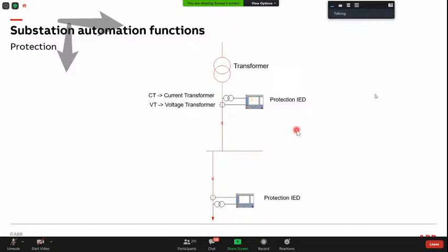And same with the voltage transformer: 765 kV on the primary side will be 110 volt on the secondary side. Through this transformation, it can know that if I'm crossing 1000 ampere here, or it is going to 1500 ampere, it will see 1.5 amperes here, and the function inside this device will understand there is something wrong. That's what I'm going to show you in the next slides. Next slide.